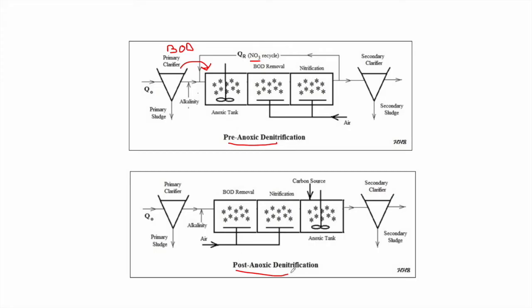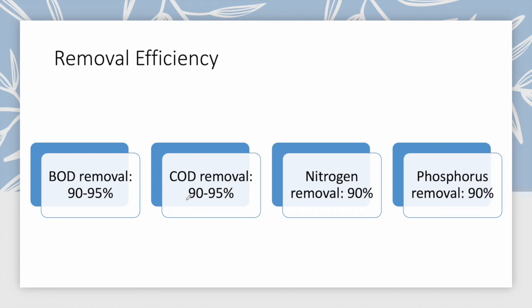For post-anoxic denitrification, since the BOD removal tank comes before the anoxic tank, we must add an external carbon source such as methanol. However, we do not face the NO3 recycling problem, because the nitrification process comes before the anoxic tank, so no recycling of NO3 is needed.